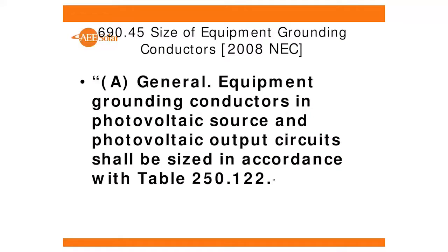And then we take that thing that's all at the same potential and we make it ground potential by connecting it through an equipment grounding conductor to earth. That way, if we have one piece of equipment connected to earth here, and another piece of equipment connected to earth there, and I happen to be able to touch both of those pieces of equipment at the same time, I don't necessarily have to have a bonding jumper between them. I know that I'm protected to earth down there. I could have a chimney or a metal vent pipe that's easily touchable from our array, which, if these things are at different potentials, could be a real problem. So that's a little bit about equipment grounding. And as I said, things got screwed up a little bit with 47D, and we'll see that in a minute.